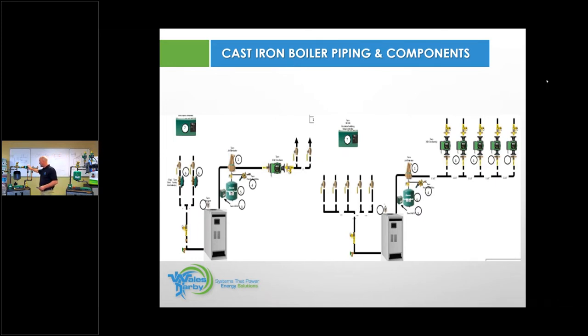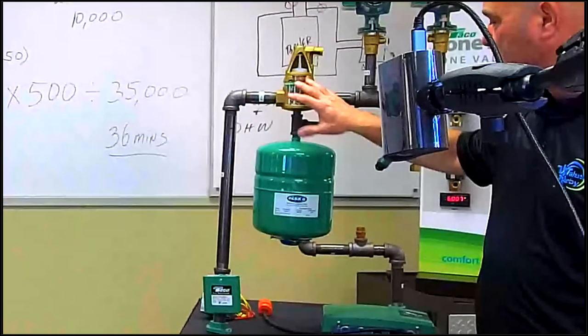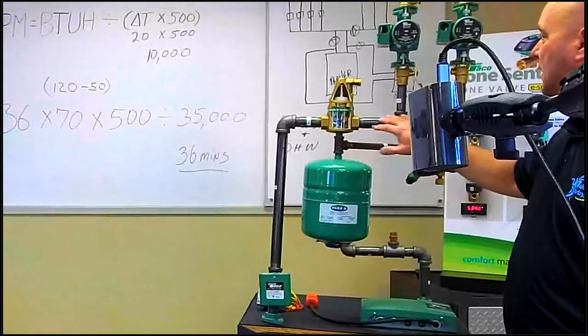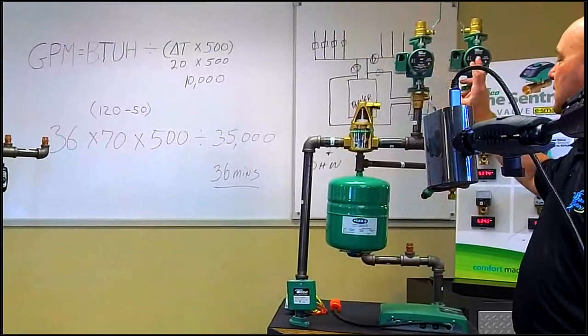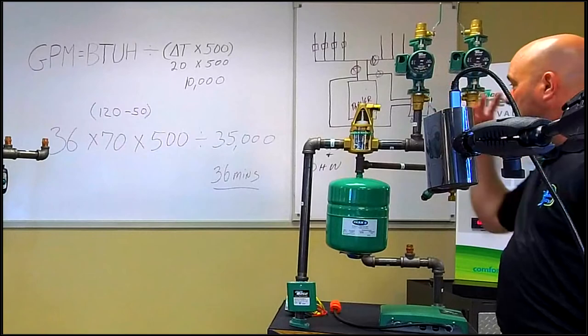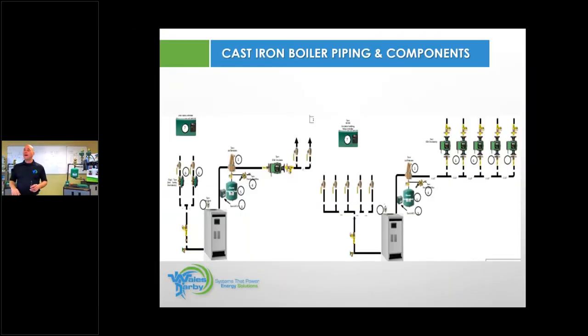And that's what we're looking at here from a zone valve standpoint. If we go over here, we have the same components, same risers, same everything, same point of no pressure drop. But here we have a two-zone circulator system. And that's just what we wanted to show. On the screen, you'll see we have a two-zone zone valve job and a five zone circulator job. So that's what we would use if it were a typical cast iron type application. Let's call it under 200,000 BTU.